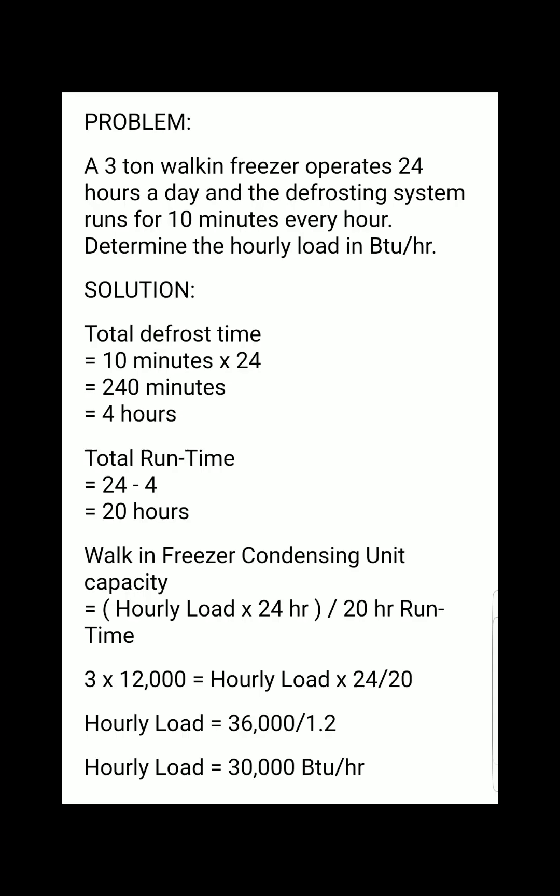To solve for the walk-in freezer condensing unit capacity, the formula is: hourly load times 24, divided by the total runtime. We have already calculated the total runtime of 20 hours, so now we substitute into the formula.